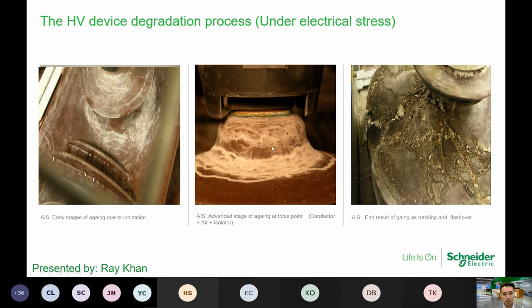Now, if all these issues are not resolved, you will start to progress into the second stage. The second stage, you can see, is called a triple point. A triple point comprises the conductor, the air and the insulator, where they actually come into play. And this is where the ionization starts to get more serious. We call it carbon staining, right? So you can see that the stains start to form a very thick layer on top of all these joints. If it's not further rectified, that is where the dangerous arcing will occur.